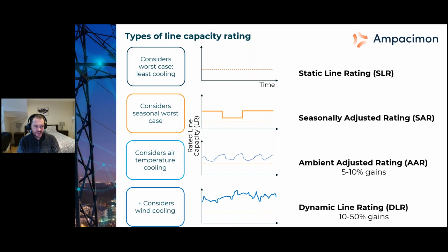And then the last frontier is dynamic line rating, where you do all of the above, but you then include the wind. And this now doesn't have a standard day-night pattern, because wind really changes, it's not dependent on day and night. It's changing all the time. It's a lot more volatile and flexible, but you can get a lot more gains. And as you can see there, you can get anything from 10 to 50% gains the majority of the time, depending on how windy this area is and what orientation the line is against the wind. Whereas AAR only gives you typically 5 to 10% gains overall.